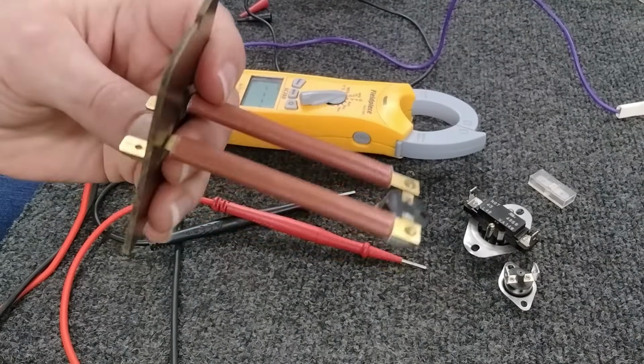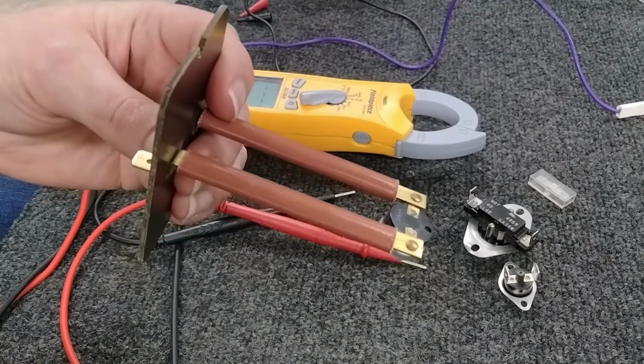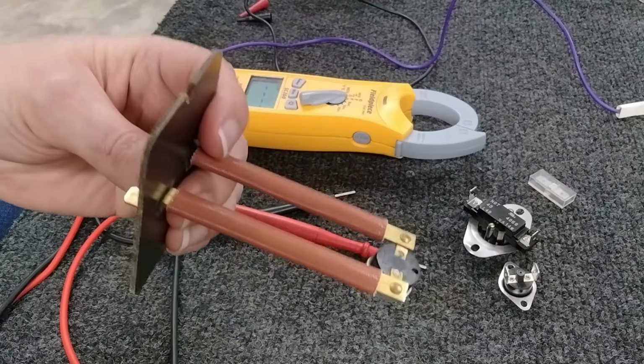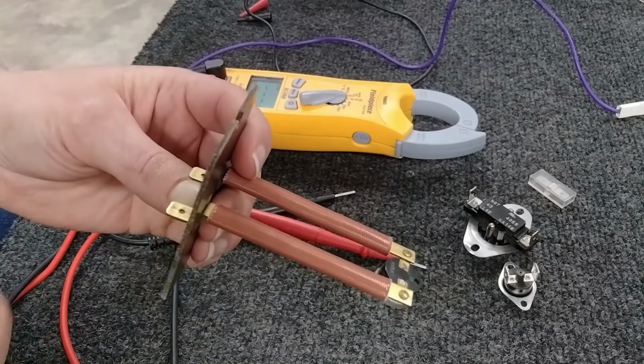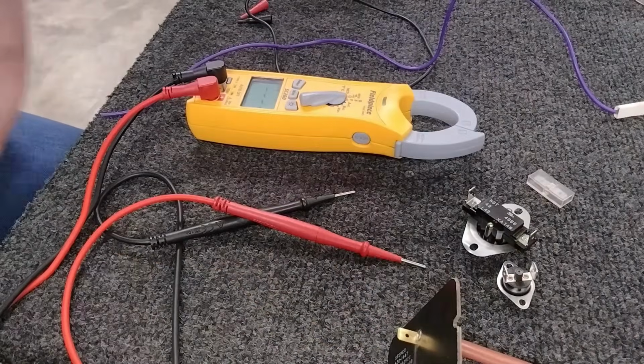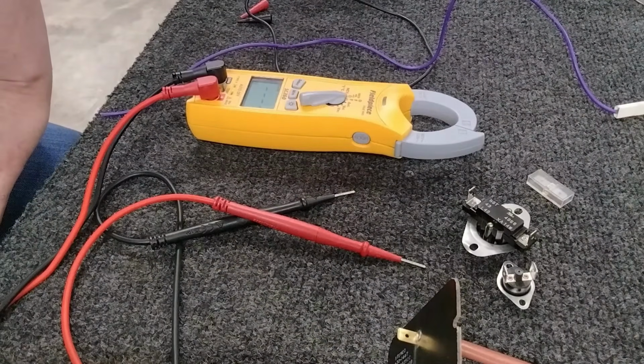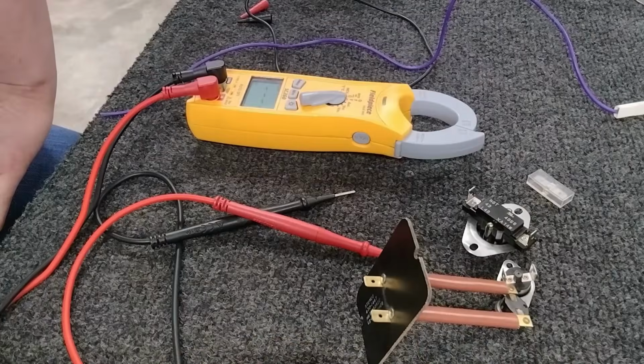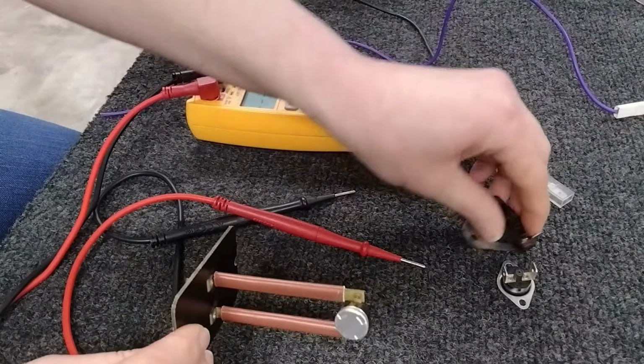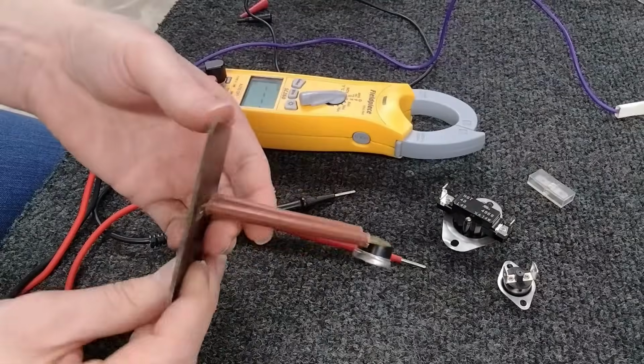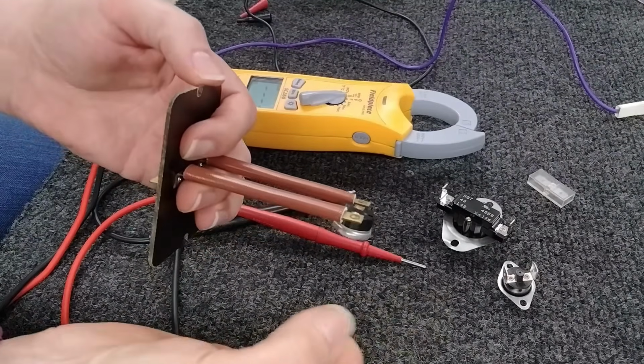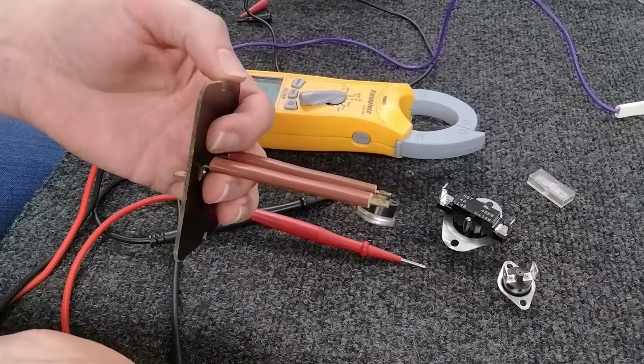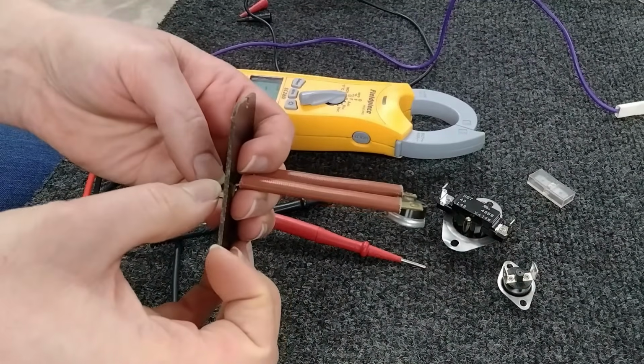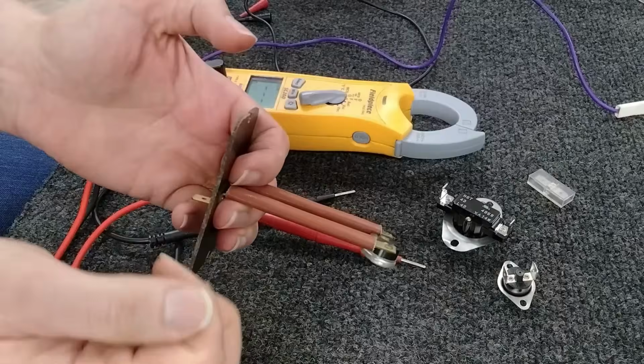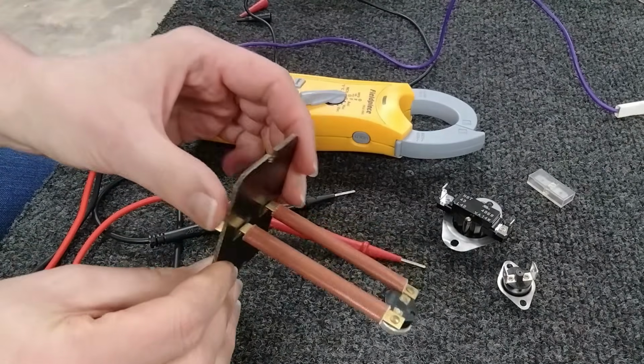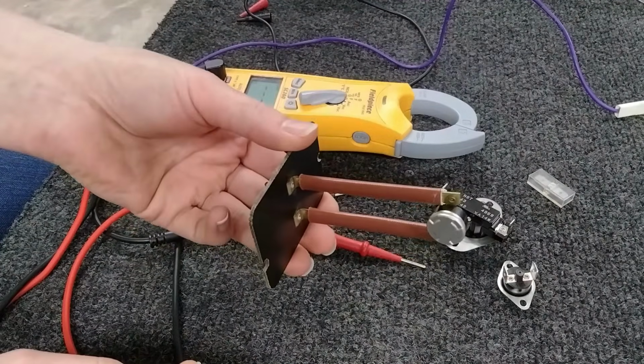Once you've tested all these for continuity, if you're not getting continuity with some of them, they could be bad. And normally, they are. It's good to check just to make sure that maybe your meter's not broken or something like that. Also, especially with these types of limits, if you're able to get continuity after thumping them, they're bad. It's time to get a new one. So if you're testing it, you don't get continuity, and you thump it, and all of a sudden it's getting continuity, go ahead and replace that, because that, again, is no bueno.